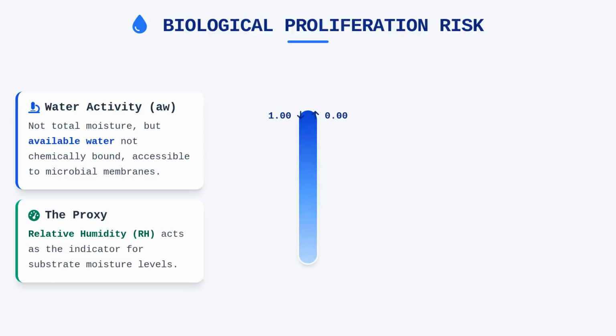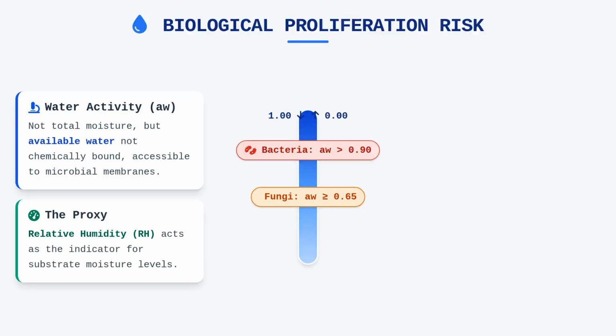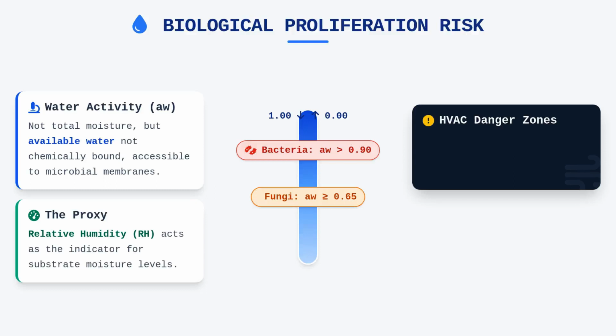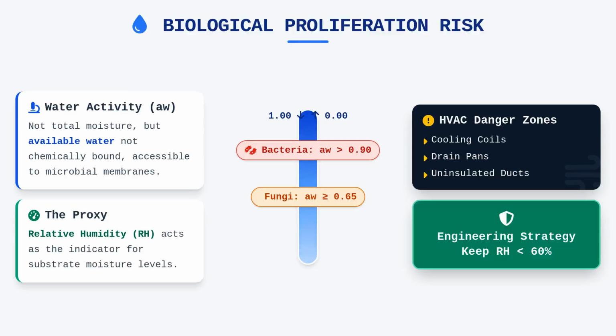Most xerophilic fungi can grow at an aw of 0.65 or higher, while bacteria generally require significantly higher levels, typically exceeding 0.9 aw. In an HVAC system, condensation on cold surfaces like cooling coils, drain pans, or uninsulated ductwork provides the high aw environment that allows colonies to develop rapidly. Relative humidity serves as a proxy for this environment, and keeping the indoor relative humidity consistently below 60% is a standard engineering strategy to prevent substrate moisture from reaching these critical biological thresholds.